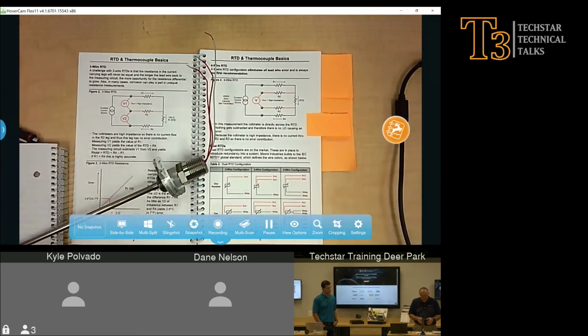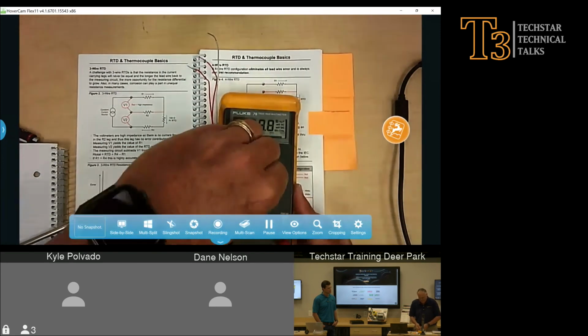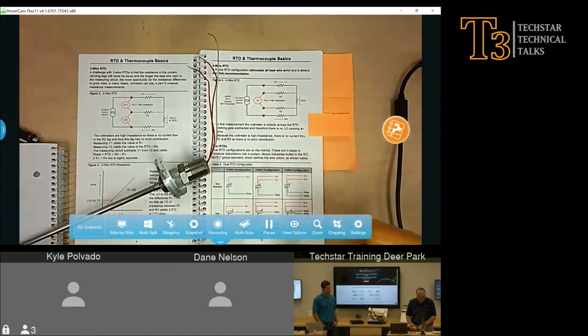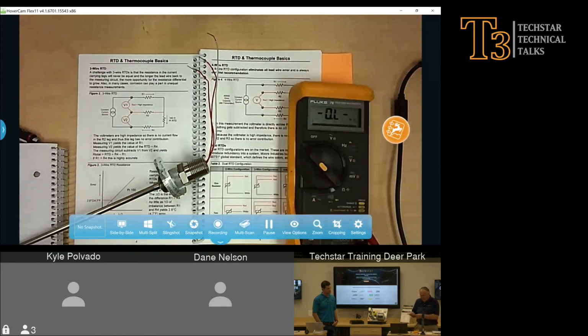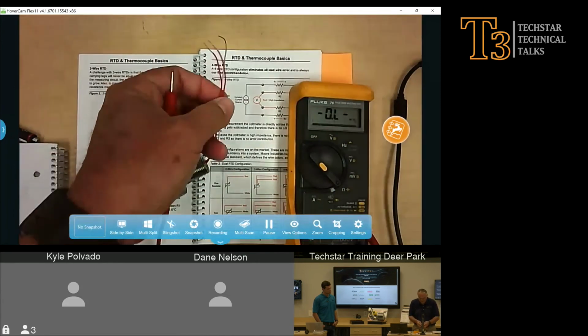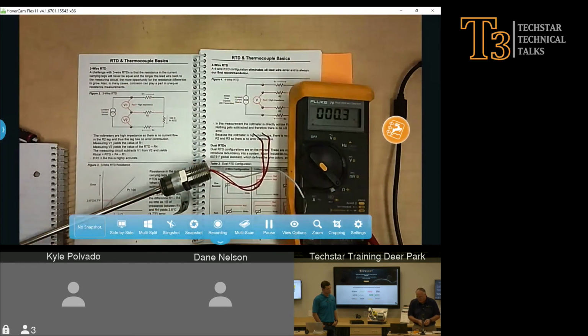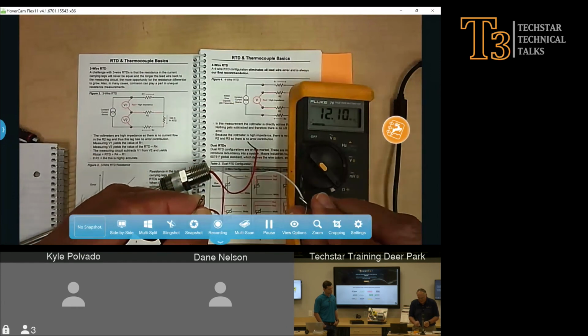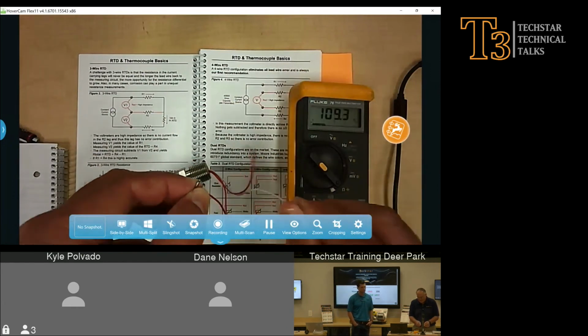It's not uncommon that we will get no directions. You've got to do RTD, and thermocouples follow a strict color standard. I'm not so sure RTDs do, but sometimes you just have to get your voltmeter out and figure out where the element is. So go over here to resistance. Of course, we cheated. We know that the reds are on both sides of the binder. The reds should be shorted together, so if I put them together, I should see 0. My meter, old faithful, so you see I'm not NIST, I'm about 3.3 ohms off. But if I put it right here, bang, I know that's it. If I take it to the white wire, I see 109. Why do I only see 100 ohms?